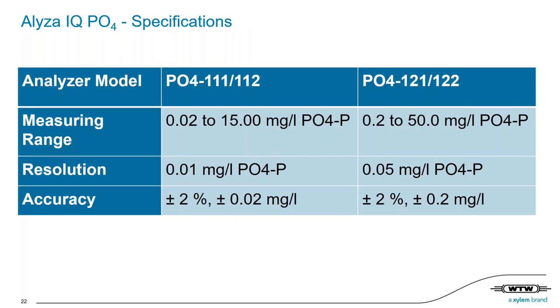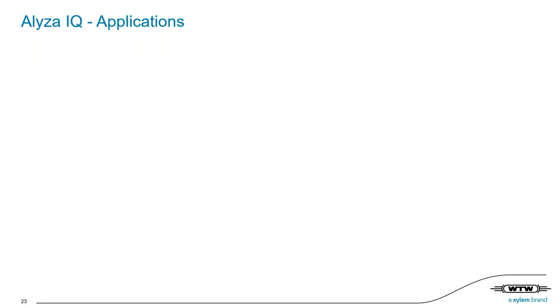Here's the specifications for the measurement. One thing is important to note. It's important to note that these are two different instrument models. So when ordering an orthophosphate unit, you need to specify which measurement range you need. If there is a need for changing the range, we can change it in the field to a different measurement range by changing out the cuvette in the photometer unit, and that's it.